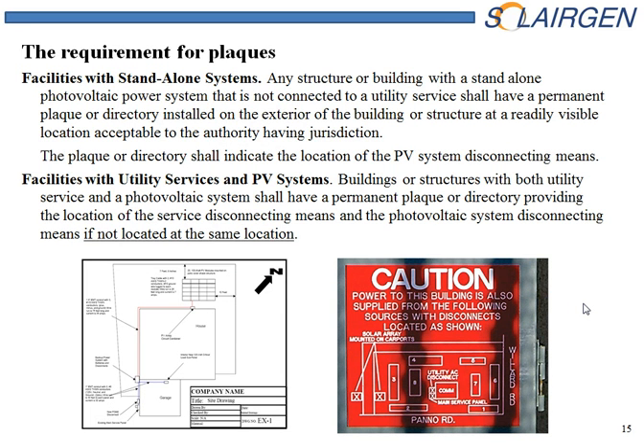Another label that's required or possibly required on standalone systems or utility interactive systems is basically a plaque or a directional label that tells you where the AC disconnect is if it is not located where you think it should be. And where would you think it should be? If it's an off-grid system, it would be where you drive up to the house or the structure. If it's a grid interactive system, it's where the meter is. So if the AC disconnect is not located where the meter is, there should be a label or directory stating where it's located.